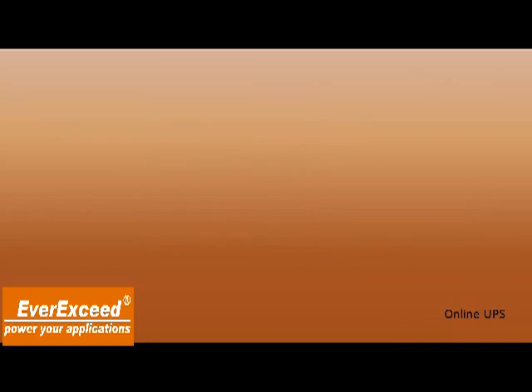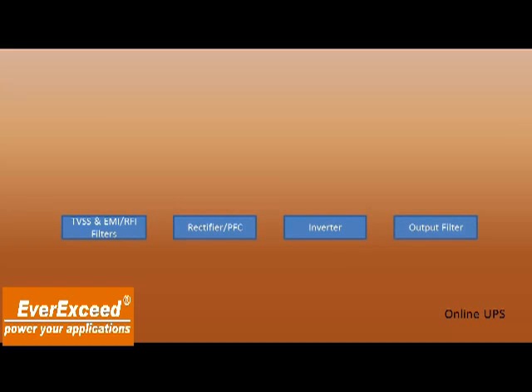The next type of UPS is the online UPS. This one uses different stages. It's quite a bit different from the standby. We start out with transient suppression and filters at input. We have a rectifier, power factor correction stage, inverter, which is what we also had with the standby, and then finally an output filter.